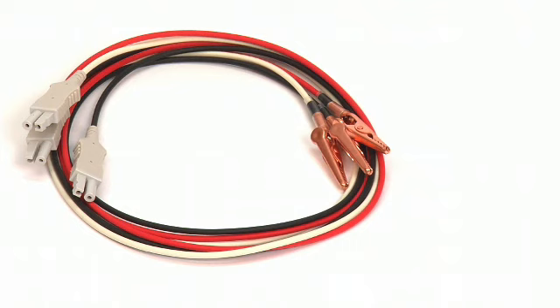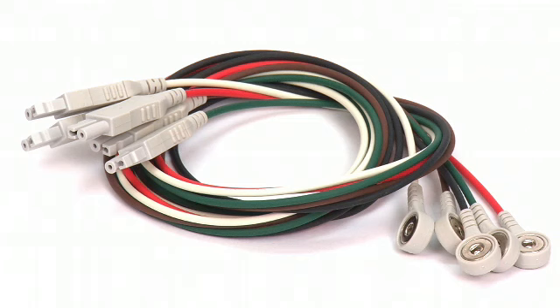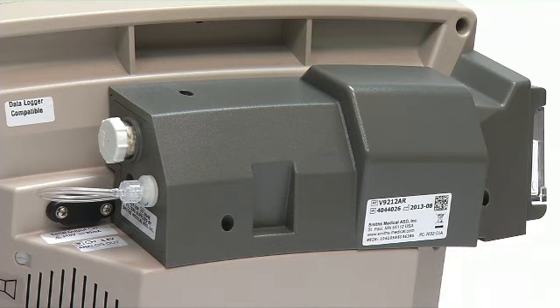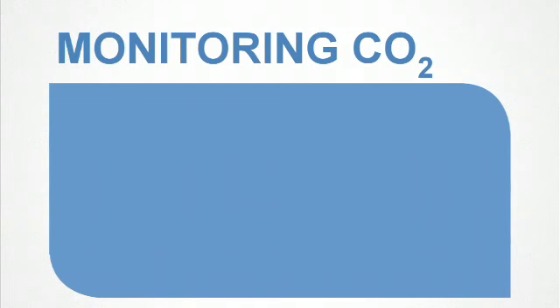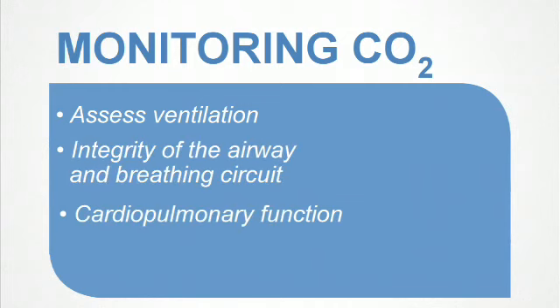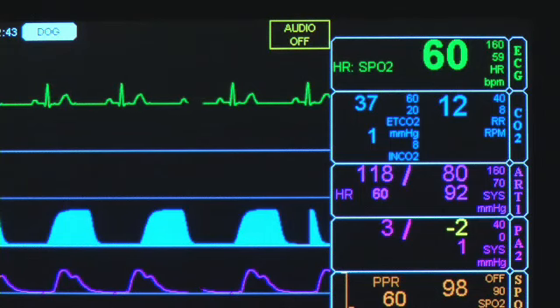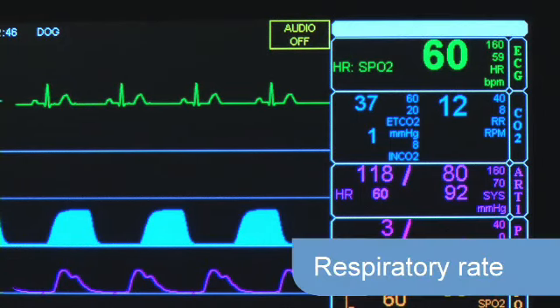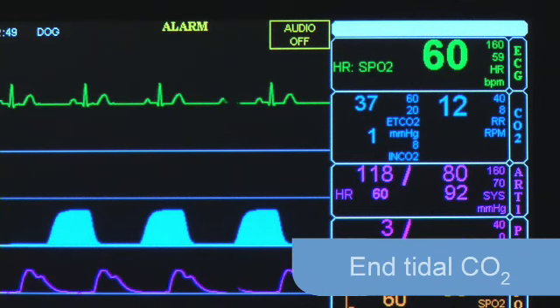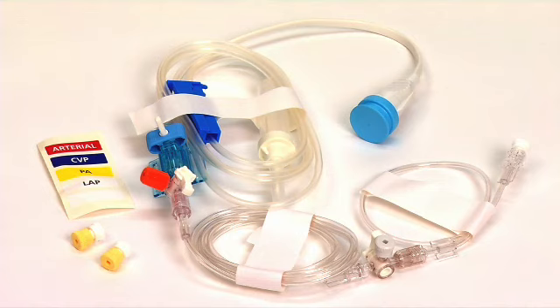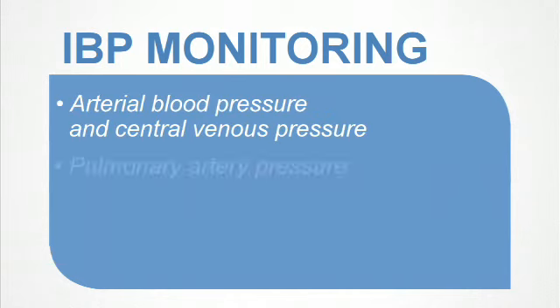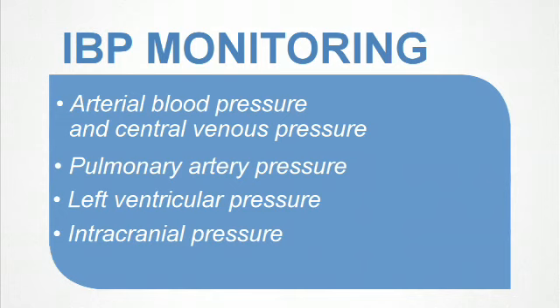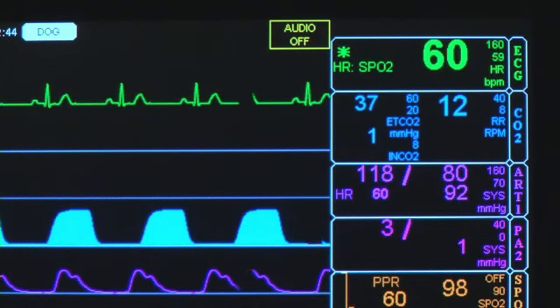The ECG leads are provided in three or five lead alligator or snap options. The Advisor Monitor features sidestream capnography as an optional parameter. Monitoring CO2 provides a means to assess ventilation, integrity of the airway and breathing circuit, and cardiopulmonary function. You can also observe the capnography waveform on the display and monitor the respiratory rate, end-tidal CO2, and inspired CO2. Optional invasive blood pressure monitoring includes two invasive pressure channels for measuring direct arterial pressure, central venous pressure, and various other hemodynamic parameters, and also features a waveform display.